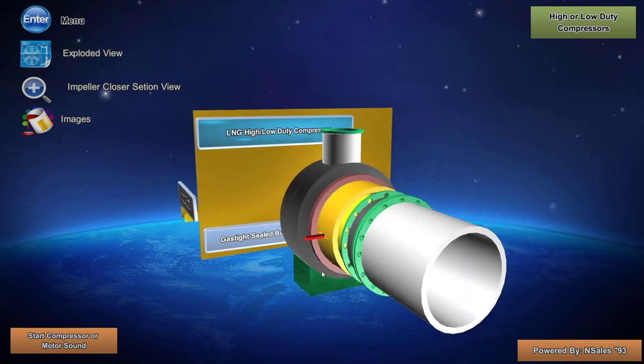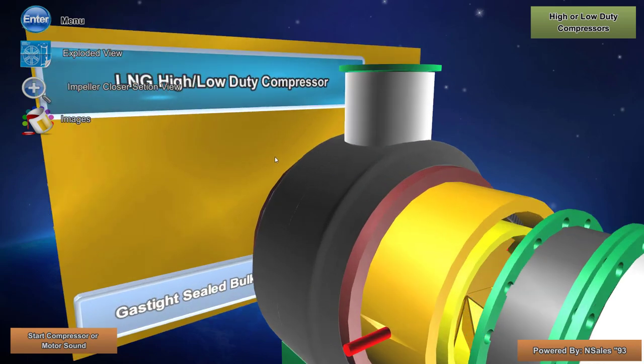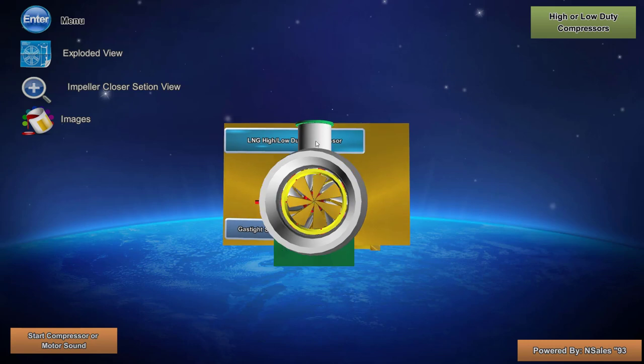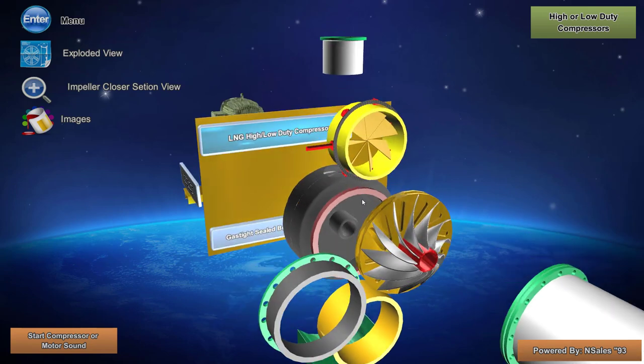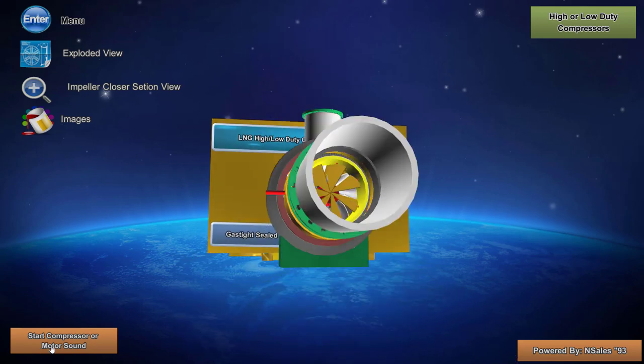This is another type of centrifugal system. Instead of a liquid passing through, it's a gas — it is being utilized on board the LNG ship and they call it high and low duty compressors, but the principles are the same. In this type it uses a vortex type of impeller casing where, as you can see, the impeller is actually in the middle and the outlet is also in the middle and the inlet is in the middle. If I blow out the image or split the assembly, you'll find the impeller, and before the impeller is the so-called inlet guide vane, which is a variable inlet guide vane. Basically, this is a so-called axial and radial, or what we call mixed flow type of centrifugal system.